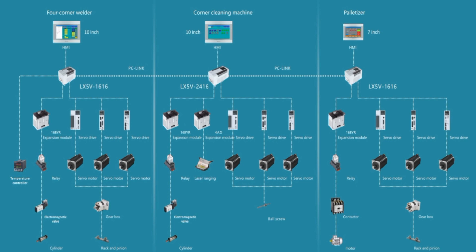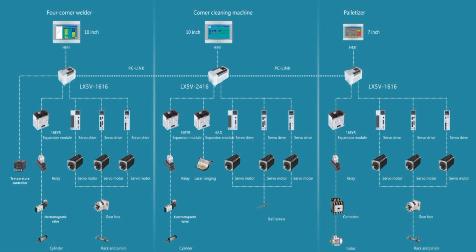This is the complete overview of the production line. Starting from the beginning: the first panel is for the corner welding machine, which has a separate HMI and separate PLC. This PLC communicates with different servo drives so the welding machine can adjust in different directions based on the size of frames. There is also a temperature controller for the heater that heats the plastic frames, and relays for solenoid valves which operate the pneumatic cylinders for clamping.